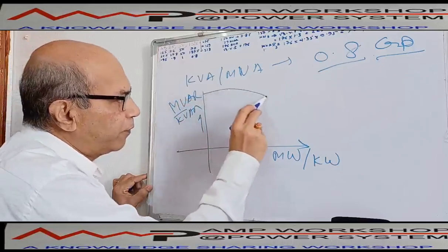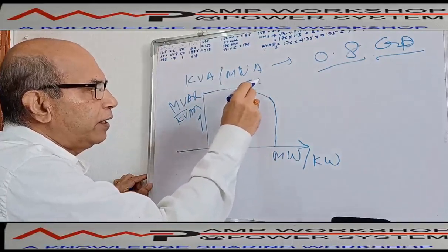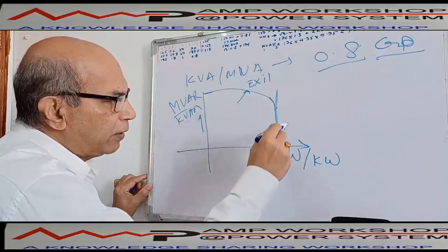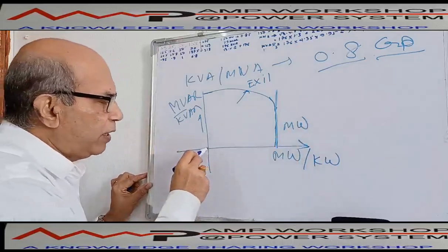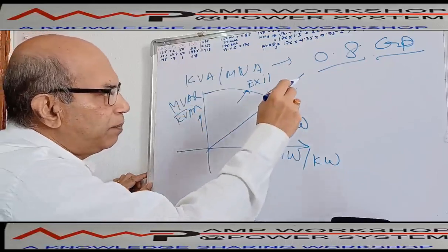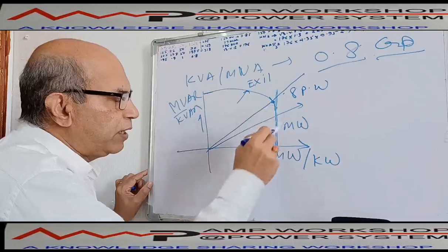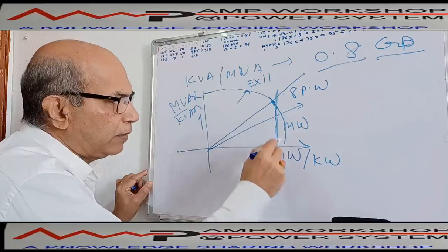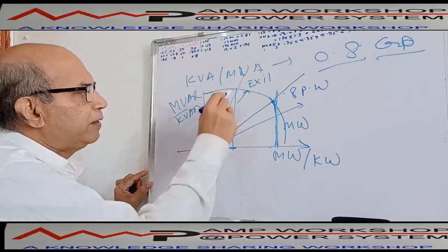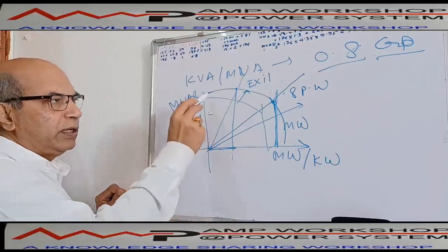Now if you see the generator capability curve, it will be like this. This area we call the over excitation area, that is MVAR, you see. And this area is called the megawatt area. Now you see here, this is the cutoff point, this point is called the rated power factor of the machine. If it is megawatt by MVAR, suppose this is a 0.8 power factor line. If you increase the power factor, then the line will go like this. As you increase the power factor, megawatt production will be increasing. But as you decrease the power factor, gradually megawatt is reducing, megavar is increasing. As you give various excitation, the curve will be like this. Depending on the excitation, the curve will be different. So this way, this is the capability curve of the generator.